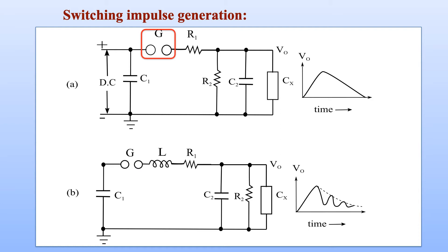Once the capacitor is charged, the spark gap G can be triggered at a desired instant so that the capacitor discharges across the test object through a wave shaping circuit consisting of resistors R1 and R2, and produces an impulse voltage, a switching impulse voltage of desired wave shape.